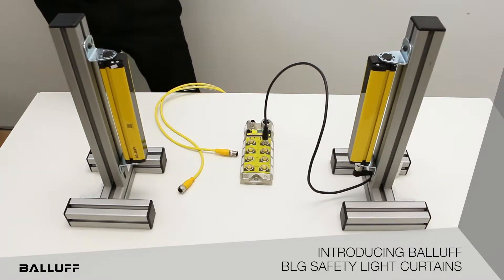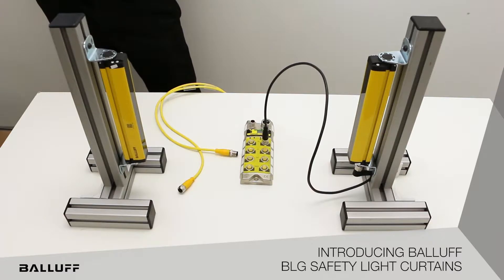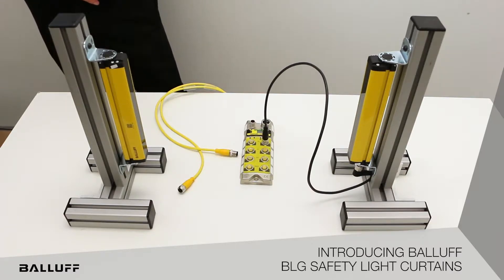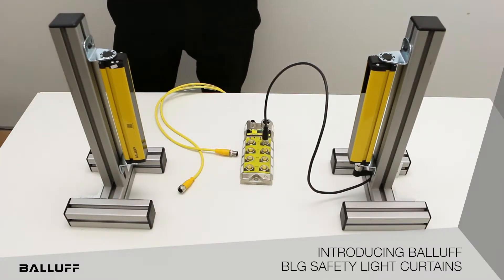The major features of the Balluff safety light curtains include the highest level of safety according to the safety standards EN ISO 13849 or IEC EN 61508, meaning they can meet the PL E or SIL 3 requirements of those standards and allow you to put those onto applications requiring that high level of safety.